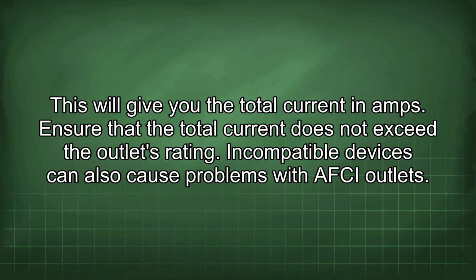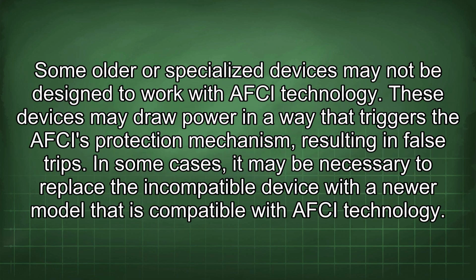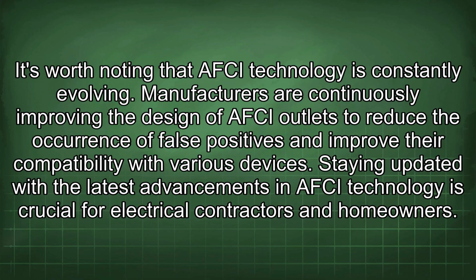Incompatible devices can also cause problems with AFCI outlets. Some older or specialized devices may not be designed to work with AFCI technology. These devices may draw power in a way that triggers the AFCI's protection mechanism, resulting in false trips. In some cases, it may be necessary to replace the incompatible device with a newer model that is compatible with AFCI technology. It's worth noting that AFCI technology is constantly evolving. Manufacturers are continuously improving the design of AFCI outlets to reduce the occurrence of false positives and improve their compatibility with various devices. Staying updated with the latest advancements in AFCI technology is crucial for electrical contractors and homeowners.